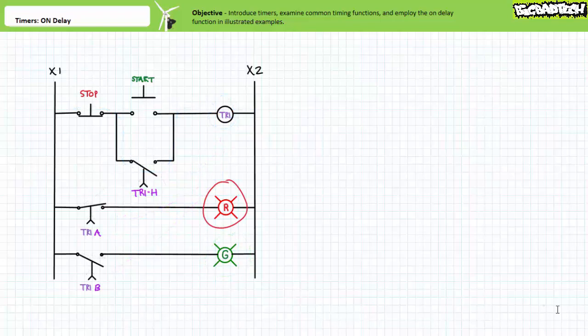The stop button de-energizes the coil of timer relay TR1 and returns the system to its start state — red light on, green light off. This is a fun example circuit that illustrates not only the function but also the utility of on-delay timers. Note this particular circuit requires the timer relay coil be continuously energized for a period of five seconds before the lights flip-flop and the holding circuit is established. We'll examine the cumulative on-delay timer in later lectures, which maintains a running tally of elapsed time despite discontinuous assertion of the controlling input.